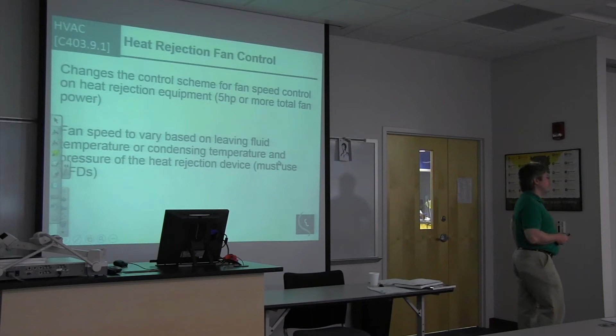Heat rejection, so your cooling towers and such, adding a control scheme for that. Noting here is how it should be controlled: fluid leaving temperature or pressure. This is a pretty small threshold, again 5 horsepower or more total, so even if you have 5 1-horsepower fans, it still counts.